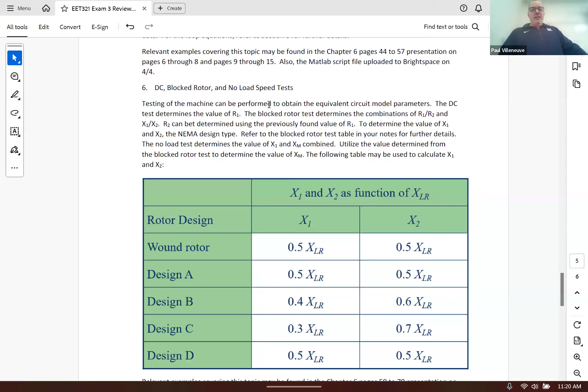Since the induction motor is rotating, we can't necessarily do an open circuit or short circuit test, because the rotor is already short circuited, so we can't open circuit that. Instead we do the equivalent from a mechanical perspective: the blocked rotor test, which is like the maximum we can have, essentially the short circuit condition, and then the no load test, or as lightly loaded or as open circuited as possible. That's the corollary between the two worlds.